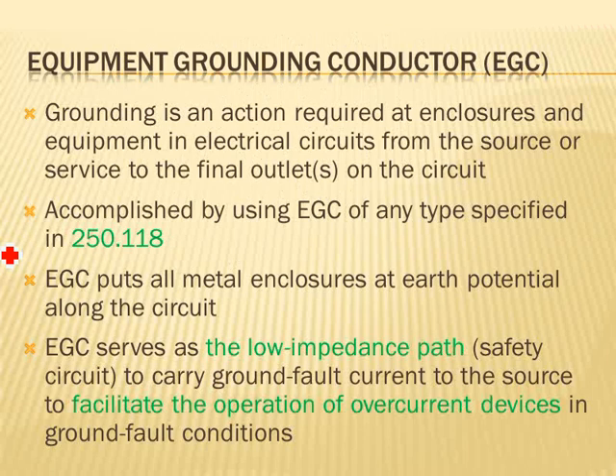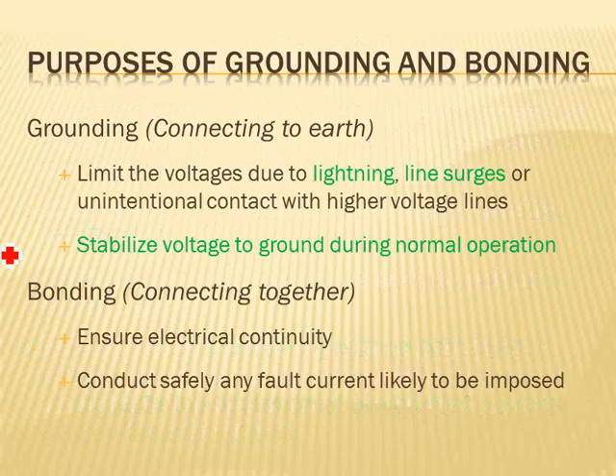Number one, how many of us walk into basements? Remember the old refrigerators, non-grounding type refrigerators? When you touch it, you get a little shock, right? So imagine how many people barefoot, like my wife, walk into the basement all the time, opening a fridge. And imagine if the fridge over that 1 year that has been sitting there, accidentally something malfunctioned. Now they have the 120 touching the frame of that fridge. Now you're looking at a hot 120 to the ground, barefoot in a basement. Let's make it in the summer when it's wet. So that's what we call the perfect shock. That's when we ground the frame of that fridge to eliminate or minimize the so-called shock hazard. And we will talk about the operation of the overcurrent device, guys, later on.